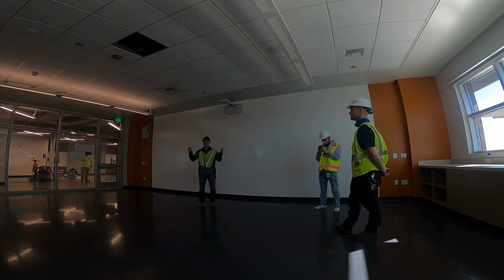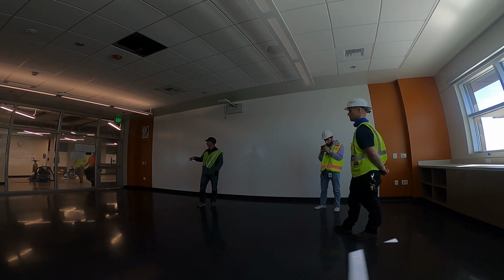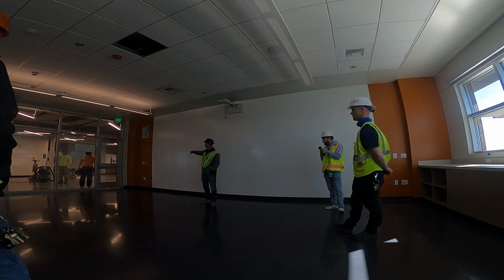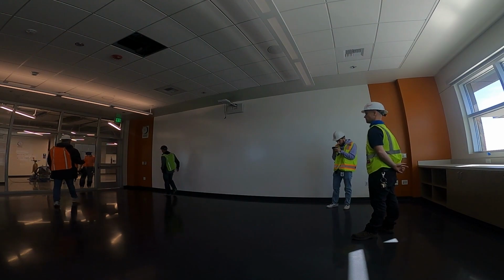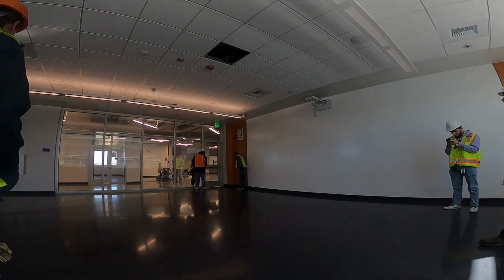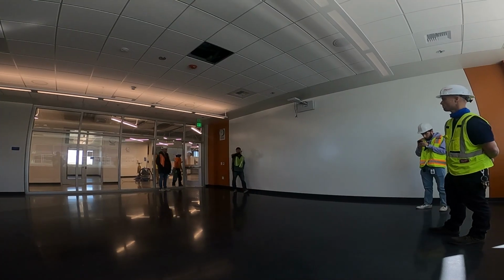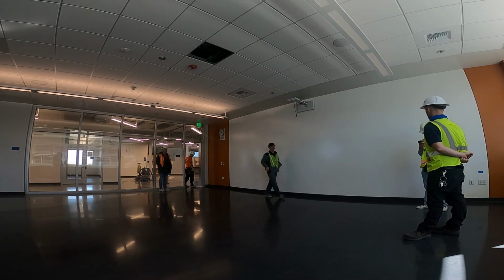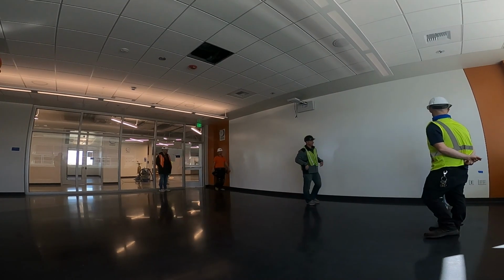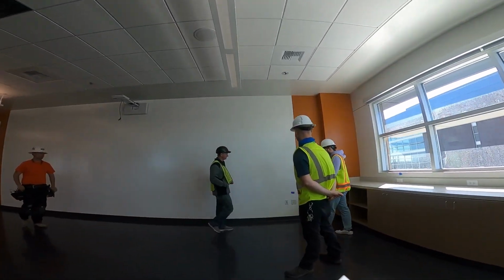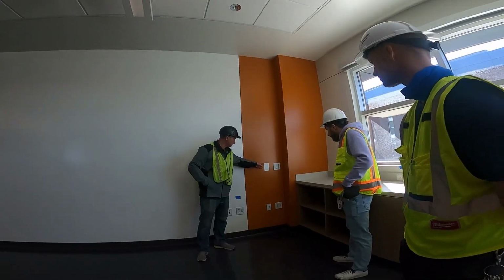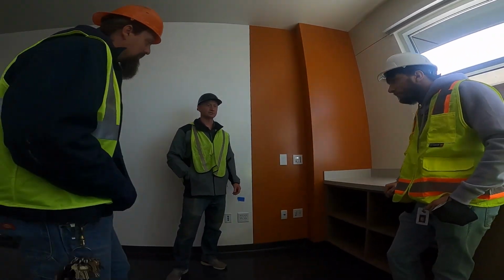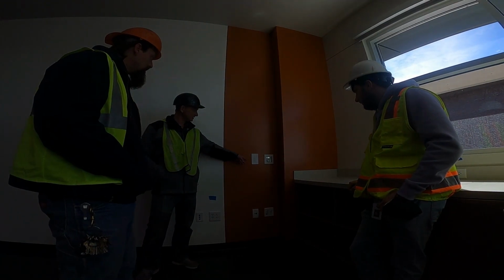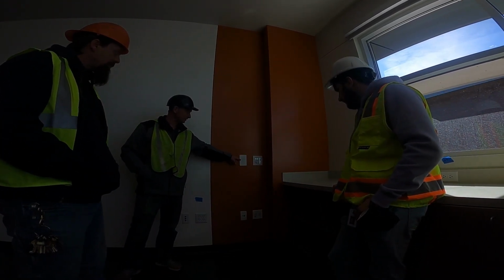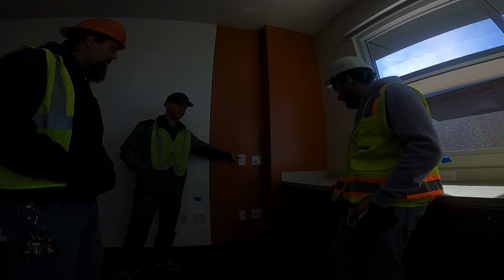It's set up for being 100% dimming there, but then you just have your on, off, and raise, lower over here for zone 1 and 2, and then over here is where you have your scenes at the teacher workstation—the switch is a little different over here. These scenes 1, 2, and 3 you could make changes to in the software. I think it's something like 20, 50, and 100, and then you've got your raise, lower, and your off button.